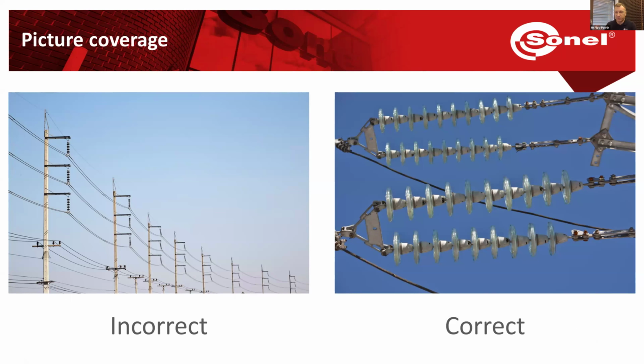Here are some visual pictures to give you the idea. Imagine we want to inspect a transmission line, and for that we look at the insulators on the line. If we stood back and took a picture of several towers of the transmission line in infrared, we'd have no idea what's going on - there would just be small dots of warmer temperature, but we wouldn't get a good idea of the temperature distribution on our object. That's why we need to take a picture, or maybe even a few pictures, of each insulator individually and check the temperature distribution on it.